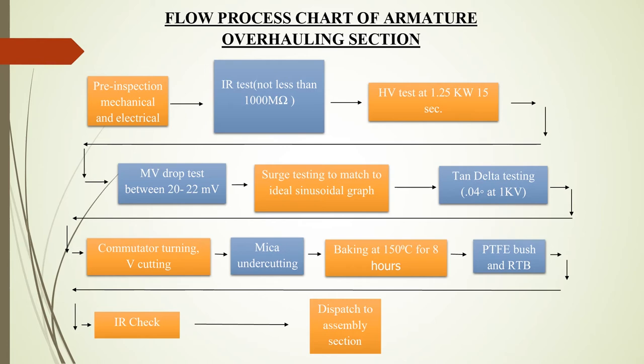Commutator turning is done to maintain a uniform gap between copper segments and carbon brushes. Commutator V-cutting is done at 45 degrees to avoid wear of carbon brushes. Chamfering and mica undercutting is done using a machine along the mica slot, with a U-cutting range of 1.25 to 1.50 mm. Baking is done at 150 degrees Celsius for 6 to 8 hours in an oven, followed by varnishing with F93 and S71. The PTFE bush and RTB sealant are fitted to prevent carbon particles from entering the gap between the cap and the commutator. Finally, a final IR test is done and the armature is dispatched to the assembly section.